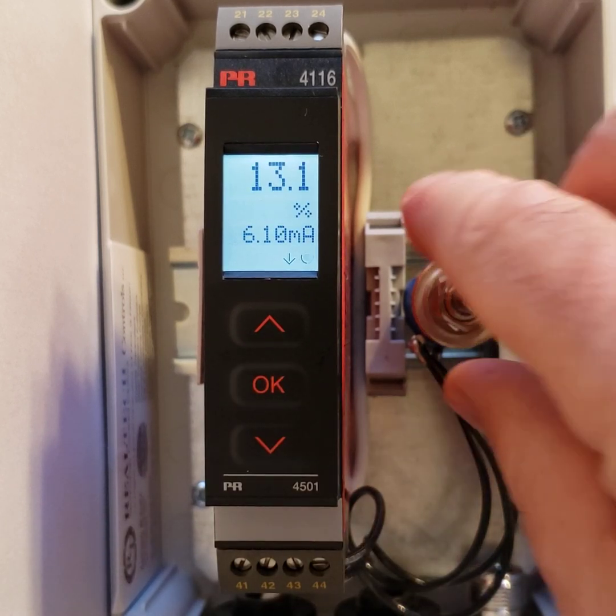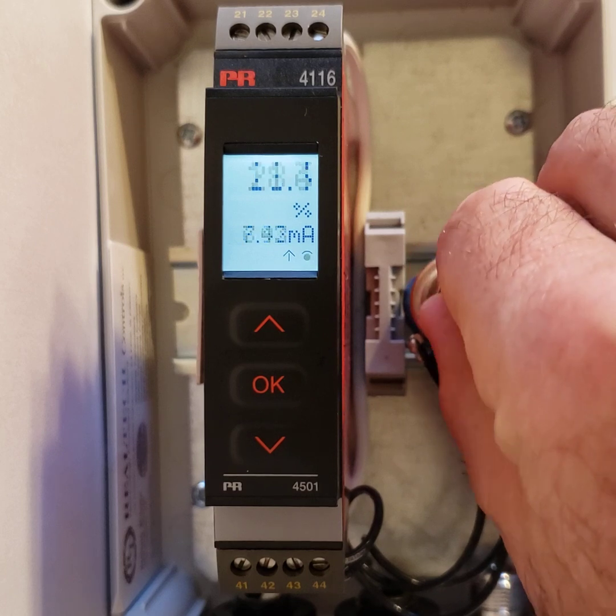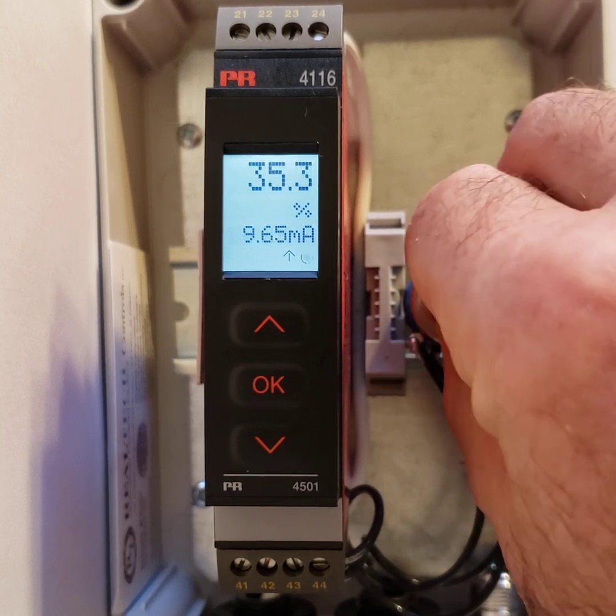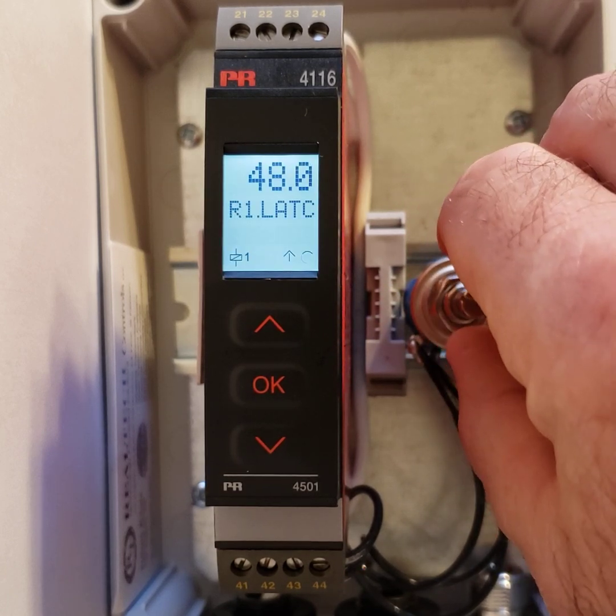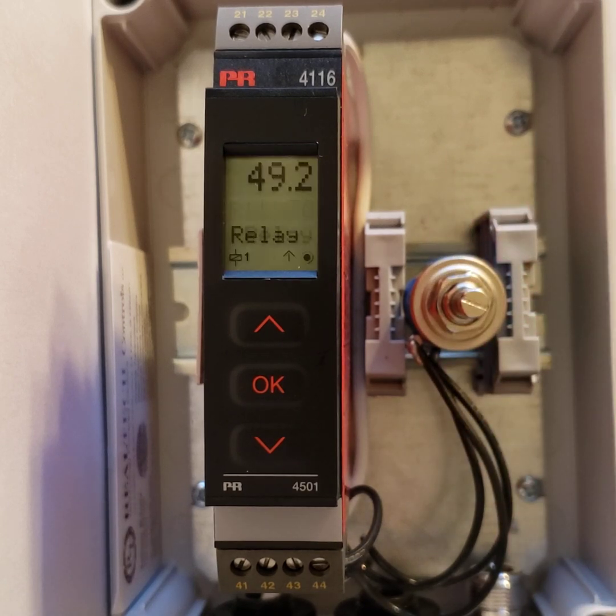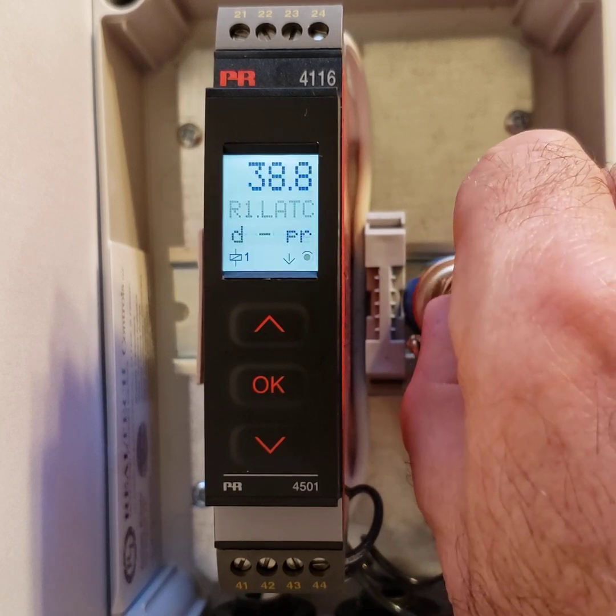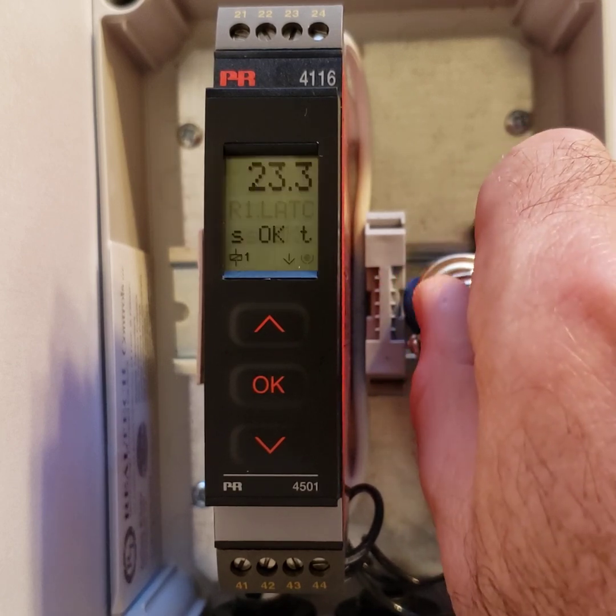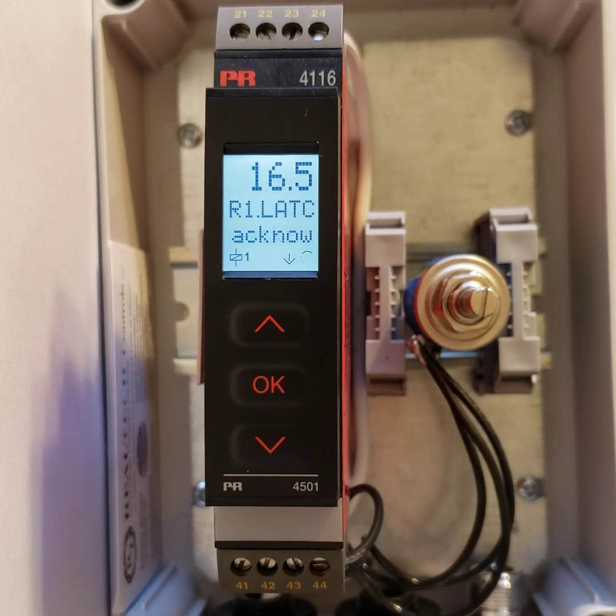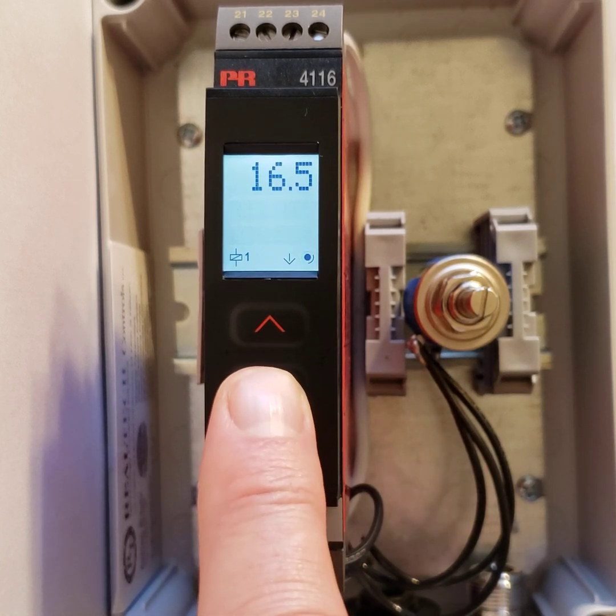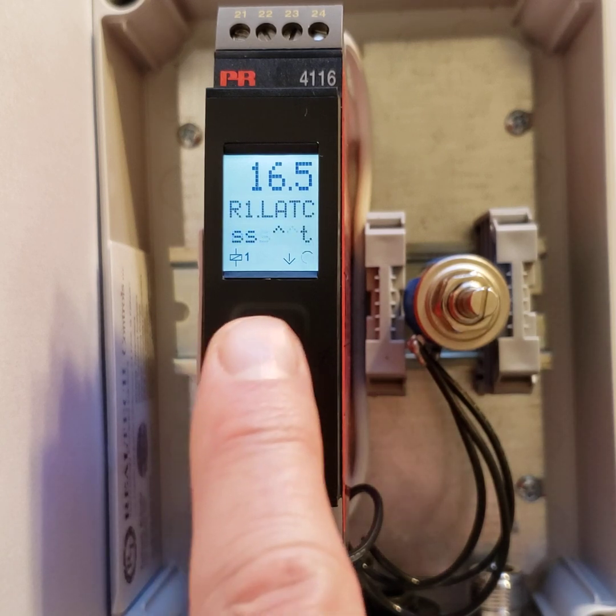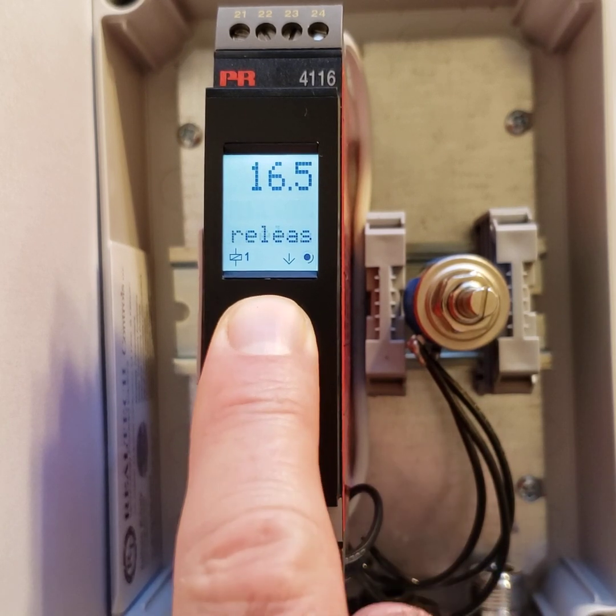So now you'll see that as I increase this and the relay latches, I think it was 48% that the relay turned on. There we go. You can see it latch. So now it's got an alarm. Even if I go below, that relay is still on because it needs somebody to come and reset that. So now the operator comes, he pushes OK, and then you have instructions saying relay one is latched. Press up to reset. I push the up arrow.